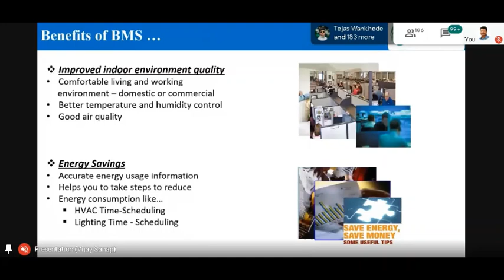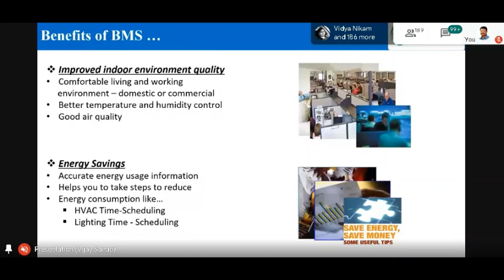Energy saving—as I've mentioned, more than 40% of energy in a building is consumed by HVAC and lighting. HVAC is heating, ventilation and air conditioning. If you schedule your chillers, say switch them off on Sunday or keep only one running out of three, and do the same with lighting by making it lux-based, you save a whole lot of energy. BMS can save 10 to 20% of energy, which unfortunately isn't recognized by people.